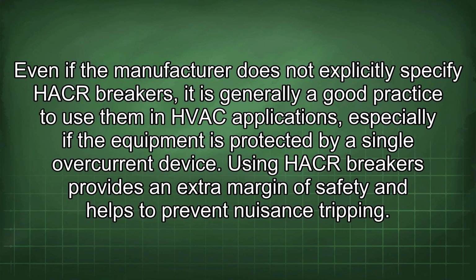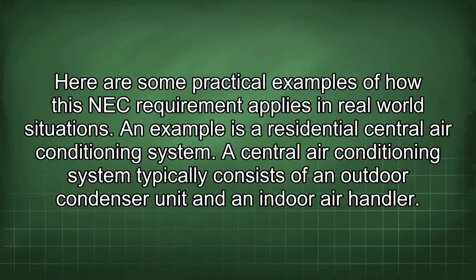Even if the manufacturer does not explicitly specify HACR breakers, it is generally a good practice to use them in HVAC applications, especially if the equipment is protected by a single overcurrent device. Using HACR breakers provides an extra margin of safety and helps to prevent nuisance tripping. Here are some practical examples of how this NEC requirement applies in real-world situations.